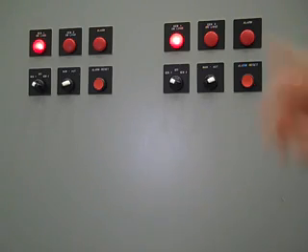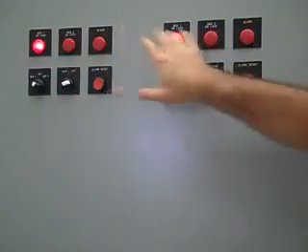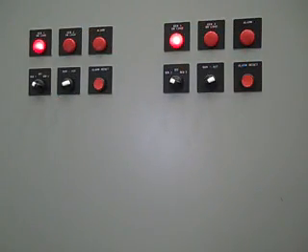Okay, so we are connected there, and right now the unit is sending a signal. There's a 30-second delay to determine that the unit has failed, and after the 30 seconds, a start signal is going to be sent. In this case, to both generators, because generator 1 was feeding switch 1 and switch 2. So in a little bit, the PLC is going to send a start signal to both Gen 2 and Gen 3.